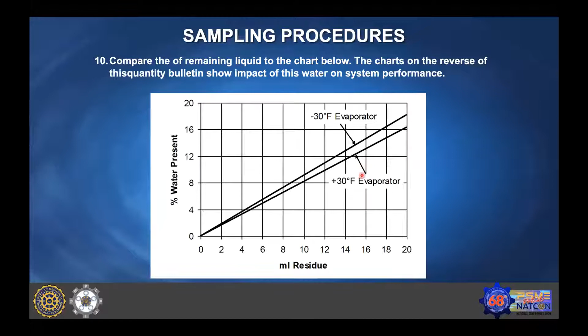So that's how I can calculate, but how do I remove the water? We can use an ammonia purifier, an ammonia dehydrator system, which removes the water. This system is provided with a coil, where the liquid is fed from the receiver and put back into the system. From the low pressure points, tappings are taken from the LP vessel outlet or the evaporator outlets and evaporator drain pipes, and brought into contact with this heat exchanger. Because of the heat in this heat exchanger, the ammonia that comes in contact gets evaporated and goes back to the system.